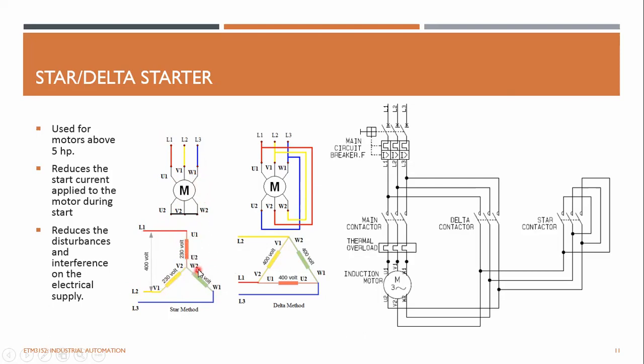So the 3 coils are connected in a star way, which means 230 volts is applied across each coil, allowing a smaller voltage, reduced torque and reduced current. This is used for motors above 5 horsepower, and for motors below 5 horsepower you can just use a DOL or direct online starter. But when it goes to power ratings more than 5 horsepower, you definitely need some sort of starting method. Star delta start is one of them.